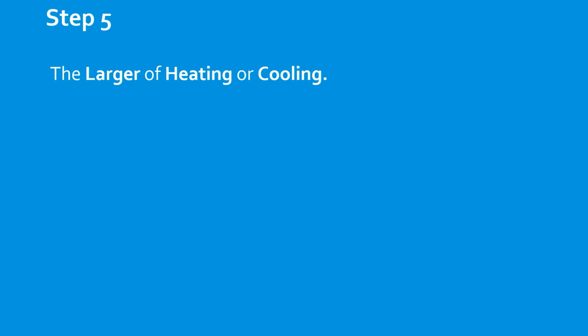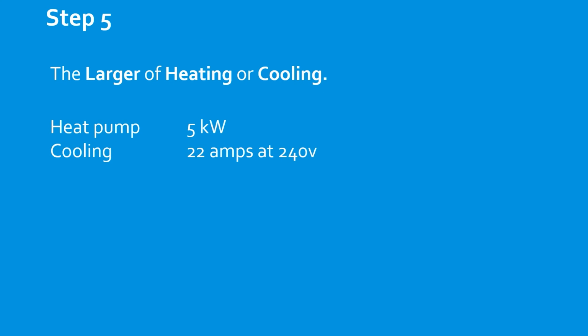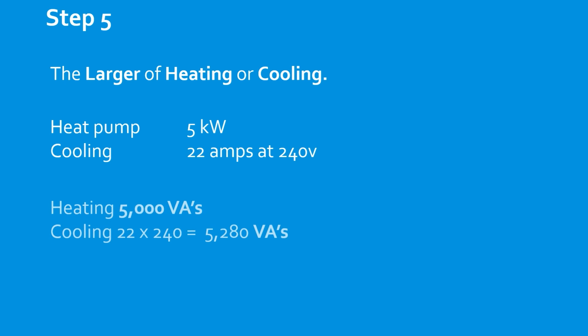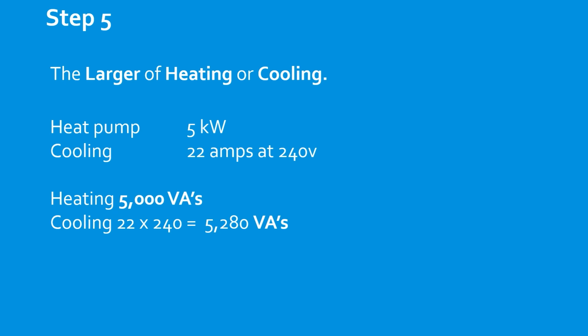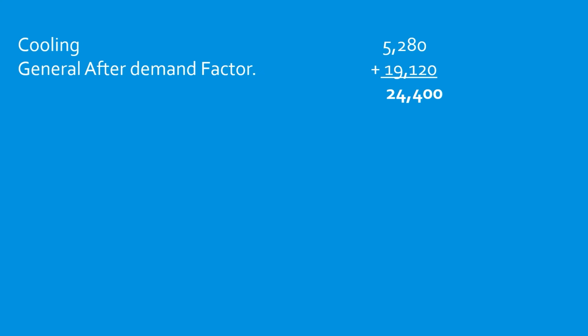Step 5, you do the larger of the heating and cooling. 5 kW and a 22 amp at 240. That is going to give us that the cooling is larger in this case at 5,280 VAs. Select the larger. That's going to give us 24,400 VAs after we add the both together. And we're going to select B.